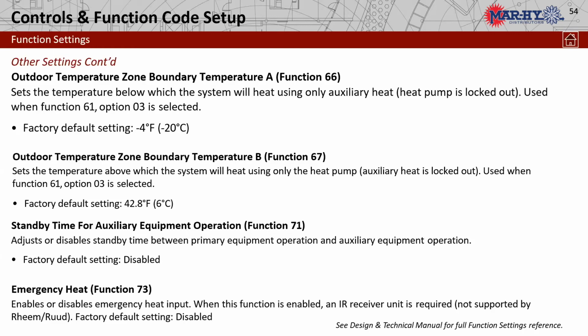So even if it is cold out there, and technically we are at factory default on that at 00 setting at -4 degrees. Let's hope we don't see that, but at -4 degrees, that will lock out the heat pump, and you will run only on auxiliary heat at that time. That's as low as we can go for a heat pump lockout. But there's no need to ever need to change that.